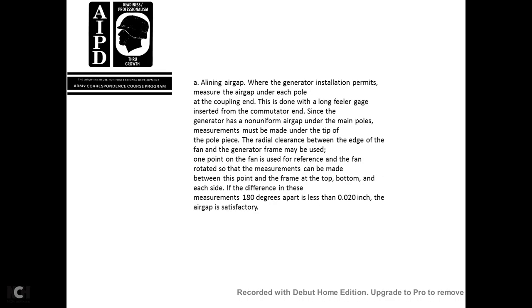The recommended place for aligning the air gap and coupling is at the engine end of the generator. The generator installation permits measuring the air gap under each of the poles and at the coupling end. This is done with a long feeler gauge inserted from the commutator end. Since the generator has a non-uniform air gap under the main poles, the measurement must be made under the tip of the pole piece, and the radial clearance between the edge of the fan and the generator frame can be used. One point of the fan is used as the reference as the fan is rotated, and the measurements can be made between that point and the frame at the top, the bottom, and each side. If the difference measured 180 degrees apart is less than 20 thousandths of an inch, the air gap is satisfactory.